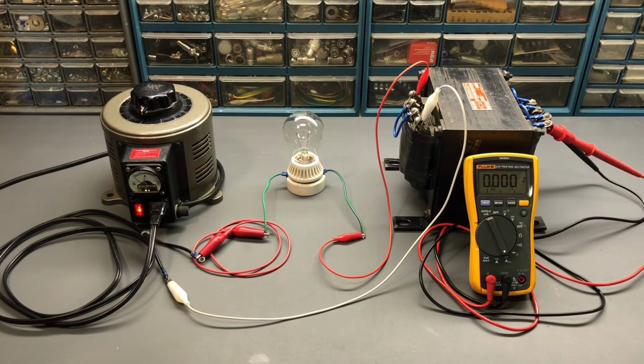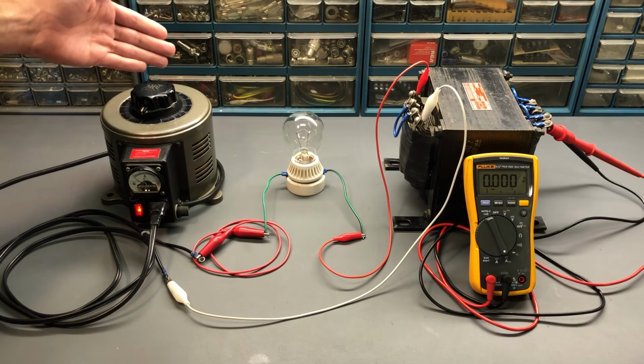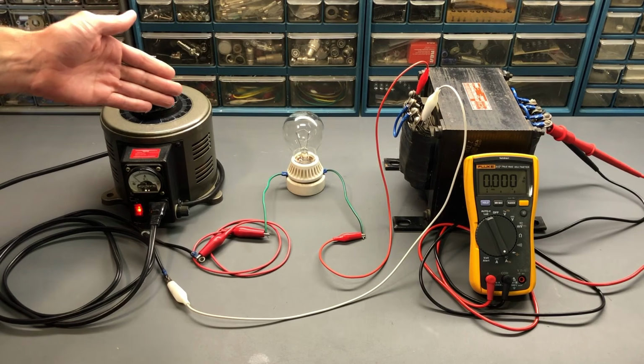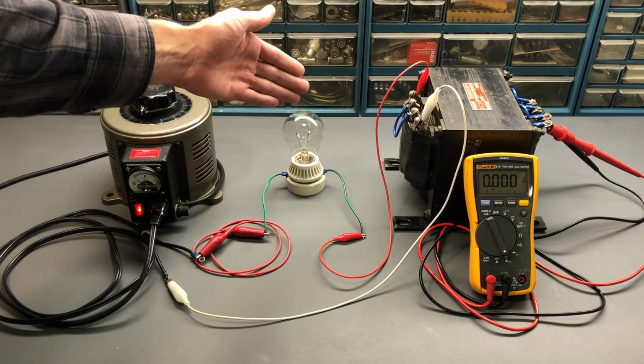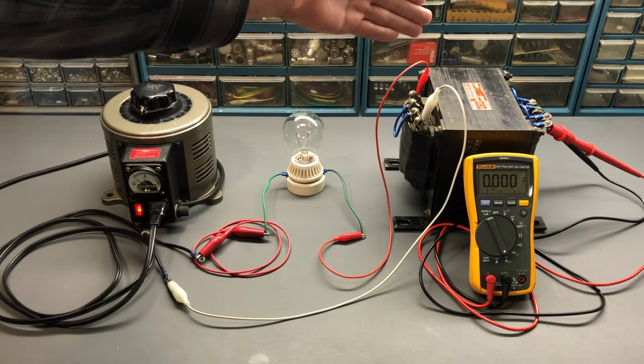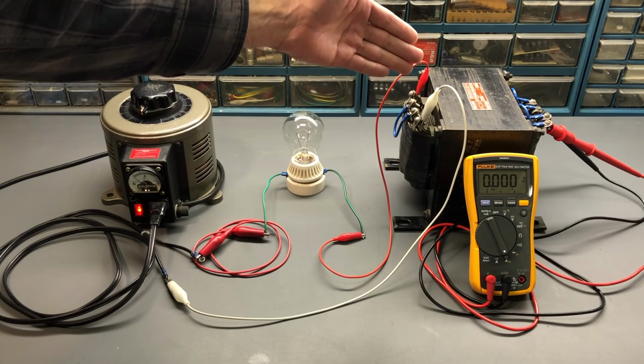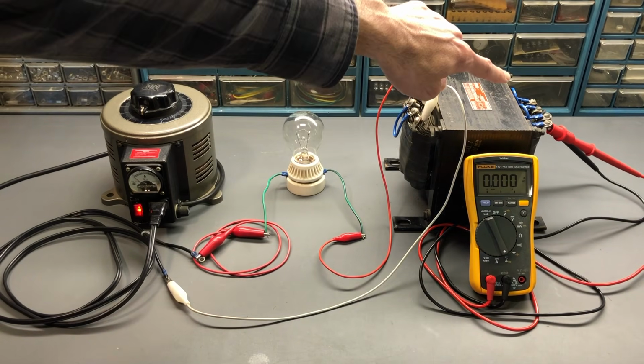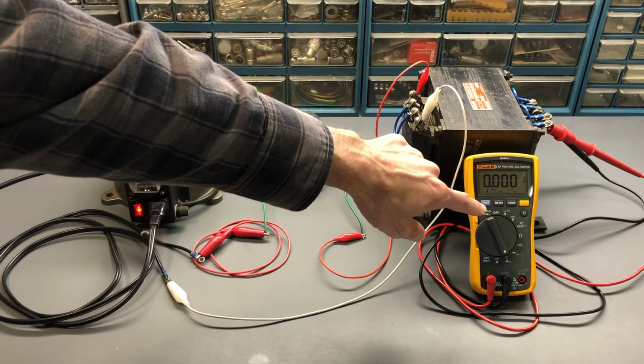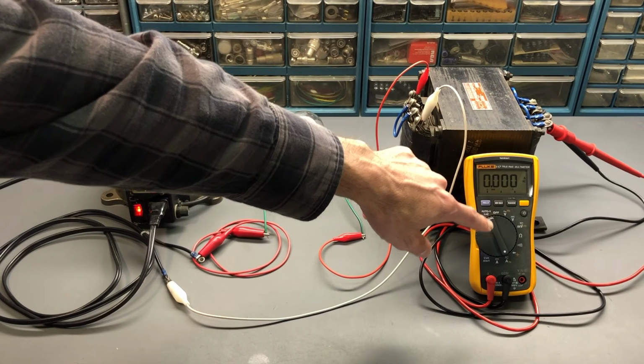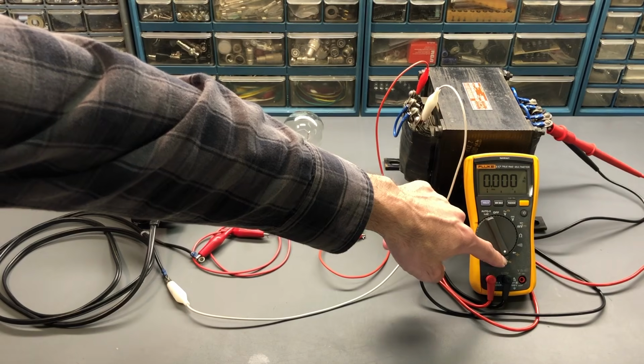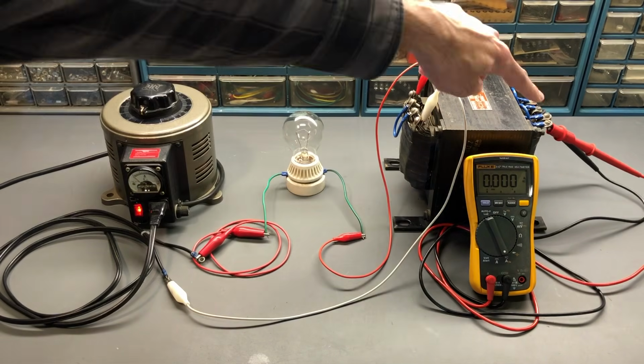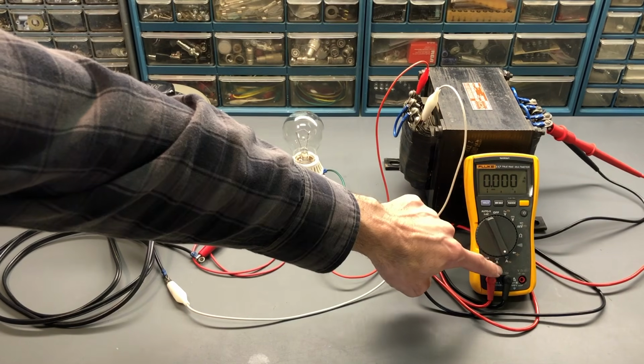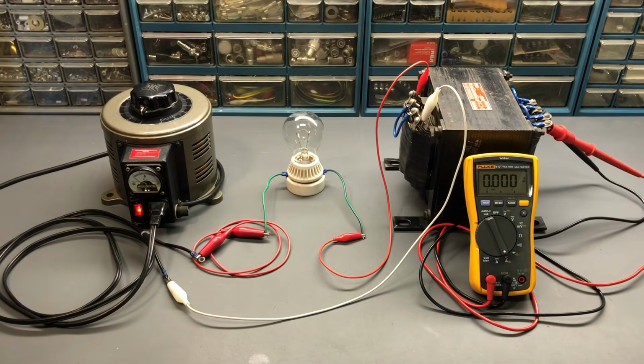Here we are looking at the second configuration of the three components. So in this configuration, we have the AC line voltage coming into the Variac first. The output of the Variac flows through the incandescent bulb, and then from the bulb it goes into the primary of the isolation transformer. So on the secondary of the isolation transformer, you can see I have the Fluke 117 digital multimeter connected, AC amps or current position, and it's connected across the secondary, so this is acting like a short circuit on the secondary.